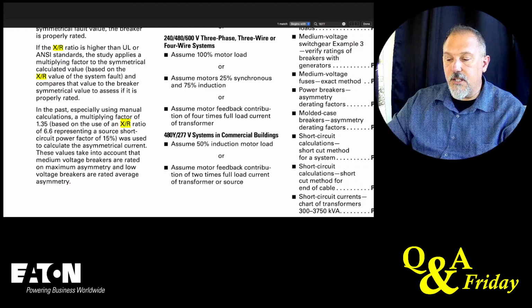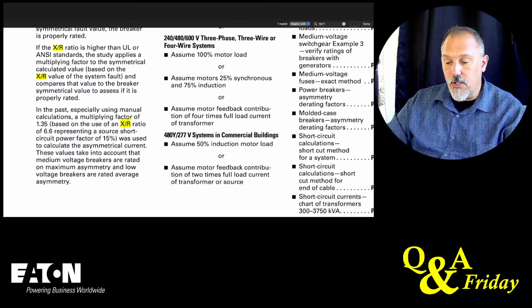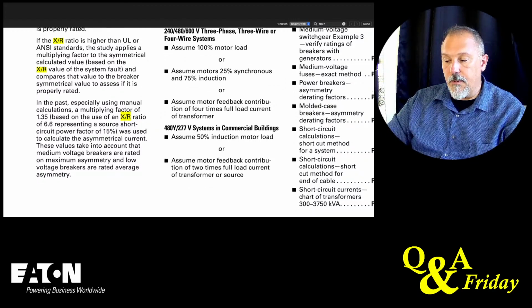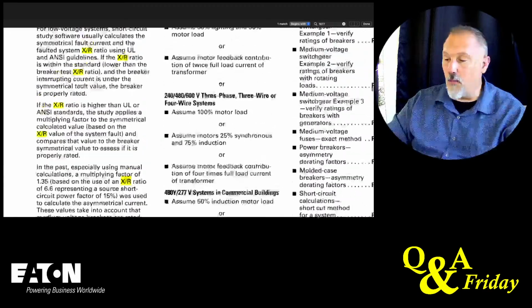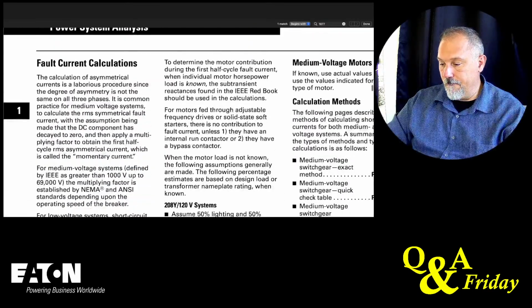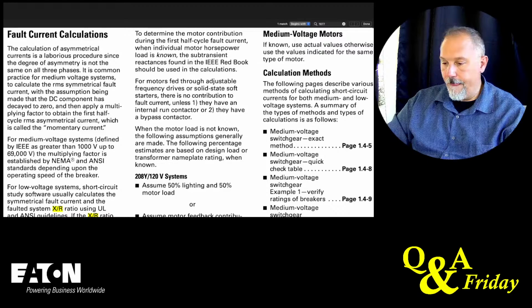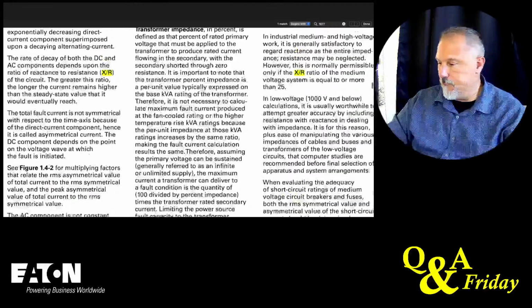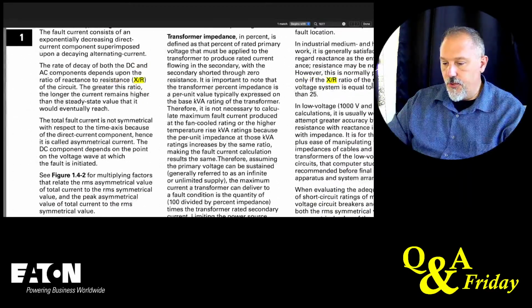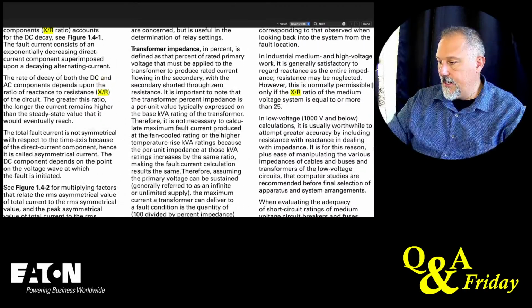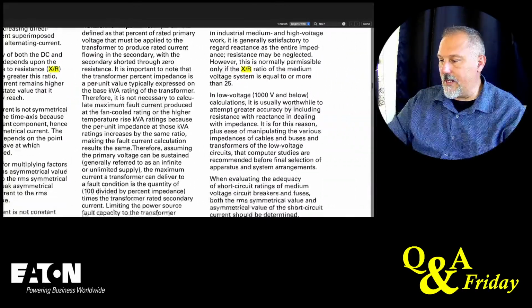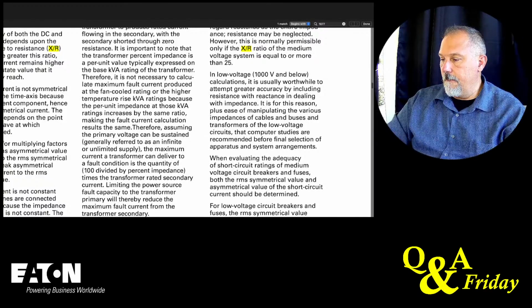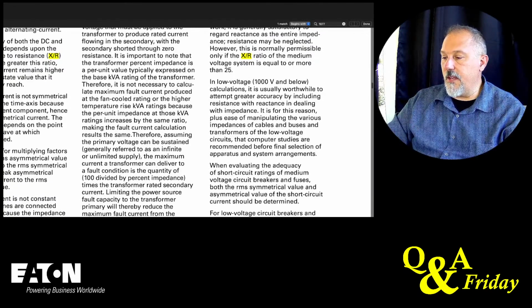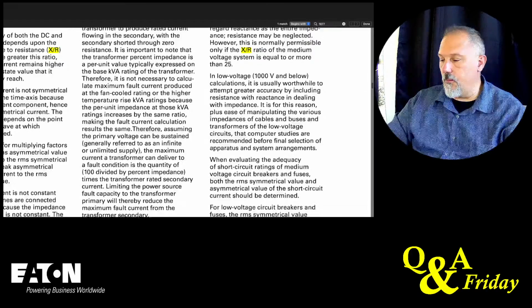Based on the use of an X/R ratio of 6.6, representing a source short circuit power factor of 15%. That's the multiplying factor. 6.6, though, is how we rate breakers. I'm looking for the adjustment factors. Industrially, it's generally satisfactory to regard reactance as the entire impedance. However, this is normally permissible only if the X to R ratio of the medium voltage system is equal to or more than 25.